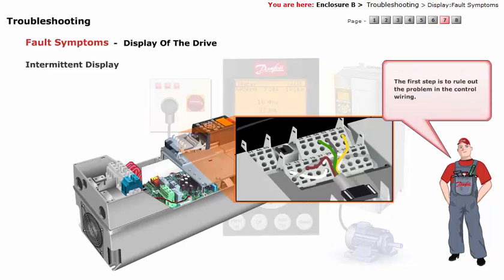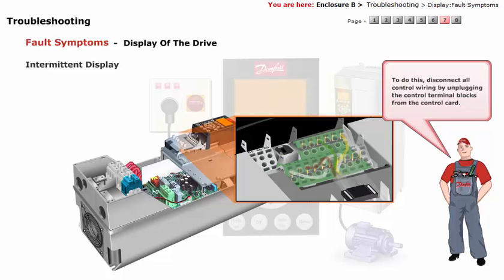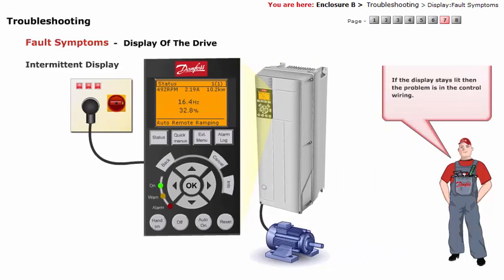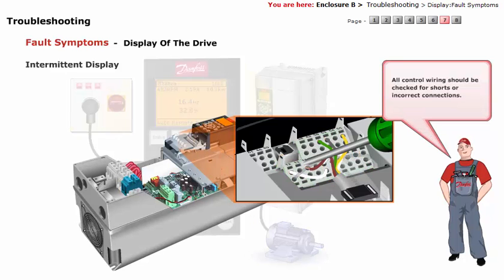The first step is to rule out the problem in the control wiring. To do this, disconnect all control wiring by unplugging the control terminal blocks from the control card. If the display stays lit, then the problem is in the control wiring. All control wiring should be checked for shorts or incorrect connections.